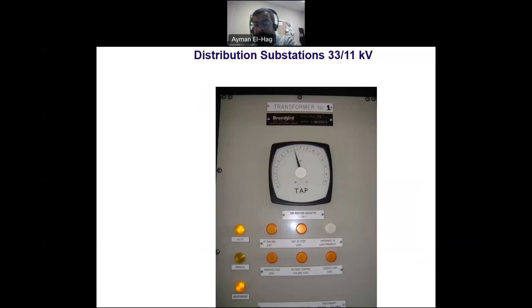This shows the actual tap selection of that specific transformer. Whenever there is a change in the tap, this will be done here, and it is in auto mode, meaning that whenever the voltage drops, you increase the number of taps. If the voltage increases, then you reduce the voltage to maintain it within certain limits. You can change from auto to manual if you want to change the tap changer manually.